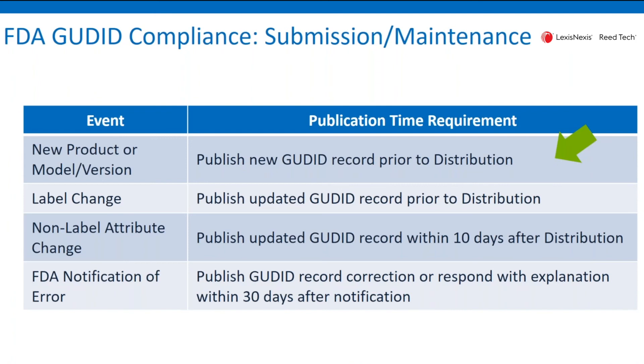For manufacturers that have already submitted their portfolio and have a lot of records in the FDA, a couple of words about maintenance. In the event that you have a new version or model of a particular product, you do need to publish a new record to the GUDID prior to distribution. If there's a change to the label values, you need to submit those updates to the FDA GUDID prior to distribution. If there's an attribute that is not on the label, then you have a grace period of 10 days after distribution to make sure that the GUDID database is updated.